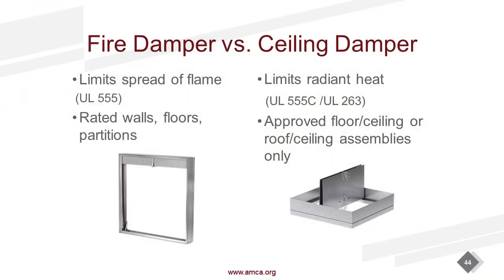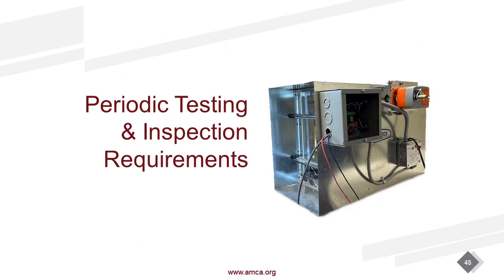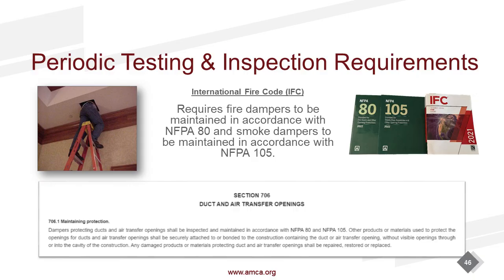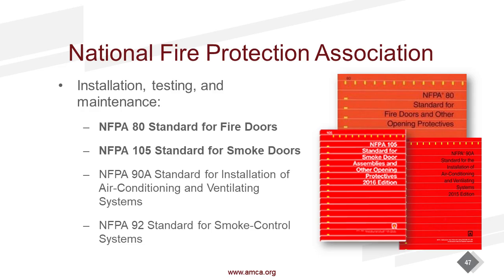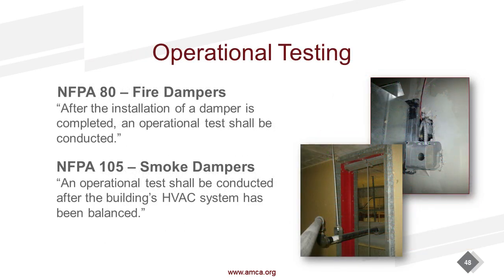So we already told you fire dampers are not ceiling dampers, and we're going to touch on periodic testing requirements. So the International Fire Code references in section 7. Basically, read NFPA 80 and 105 for your testing requirements. And in them, basically after you install a damper, contractors test to make sure it works, right? That's how our operational test is conducted. Then 1 year after that, the damper is tested again. And then 4 years after that, I test my damper again, and then every 4 years, I test that damper, unless I'm a hospital, and it's every 6 years.